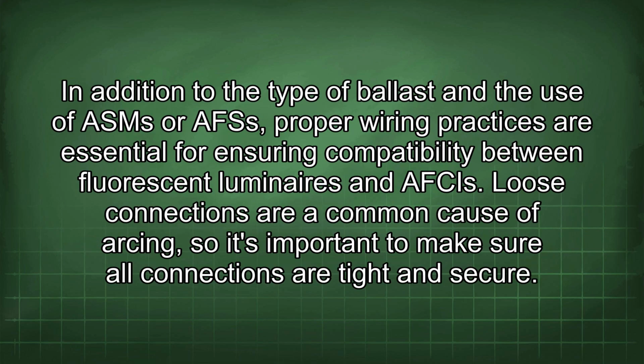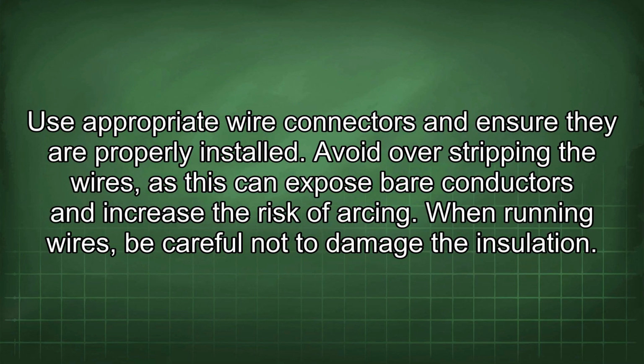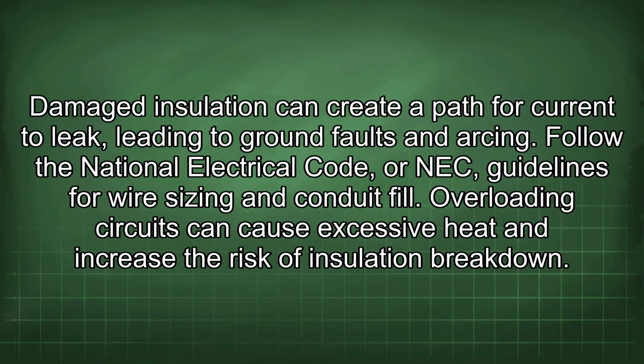In addition to the type of ballast and the use of ASM or AFS, proper wiring practices are essential for ensuring compatibility between fluorescent luminaires and AFCIs. Loose connections are a common cause of arcing, so it's important to make sure all connections are tight and secure. Use appropriate wire connectors and ensure they are properly installed. Avoid overstripping the wires, as this can expose bare conductors and increase the risk of arcing. When running wires, be careful not to damage the insulation. Damaged insulation can create a path for current to leak, leading to ground faults and arcing.